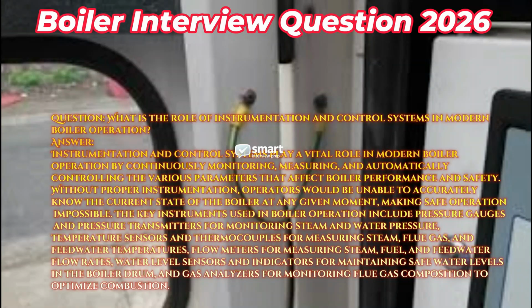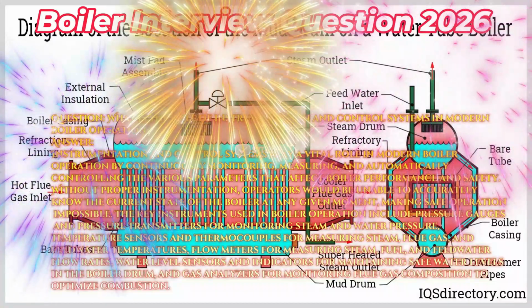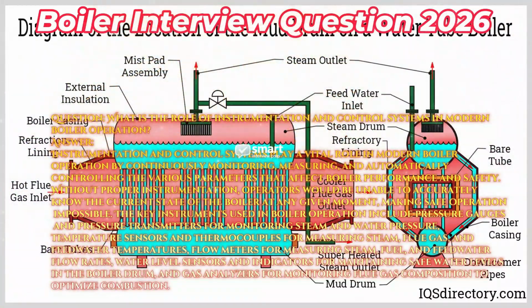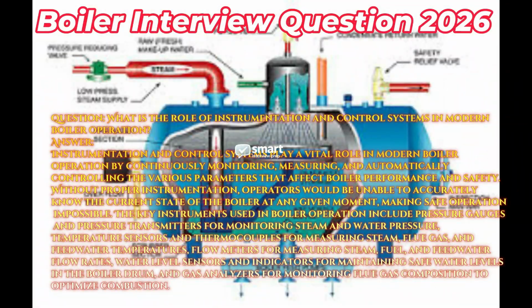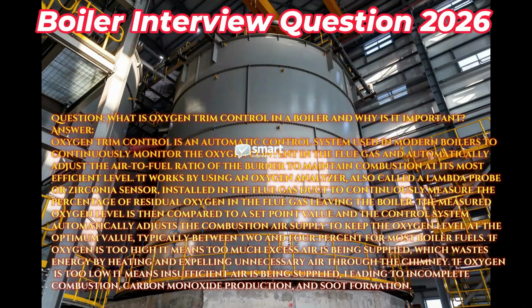The key instruments used in boiler operation include pressure gauges and pressure transmitters for monitoring steam and water pressure, temperature sensors and thermocouples for measuring steam, flue gas and feedwater temperatures, flow meters for measuring steam, fuel and feedwater flow rates, water level sensors and indicators for maintaining safe water levels in the boiler drum, and gas analyzers for monitoring flue gas composition to optimize combustion. Question: what is oxygen trim control in a boiler and why is it important?